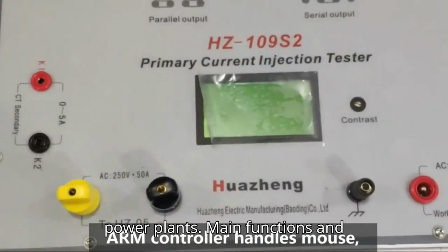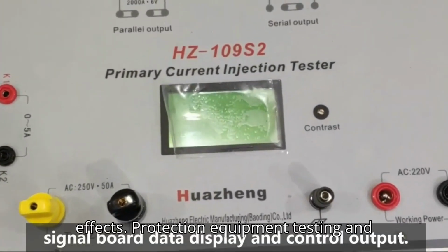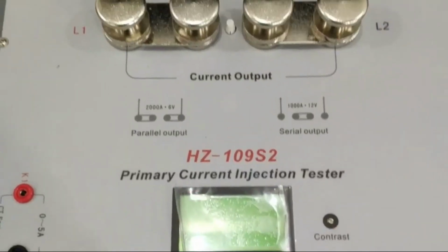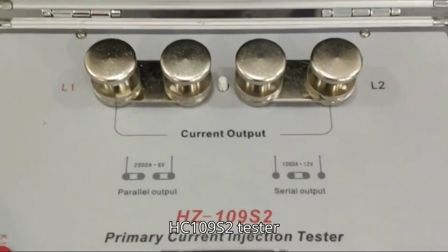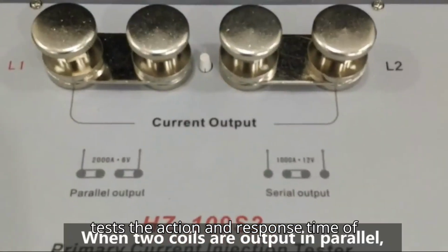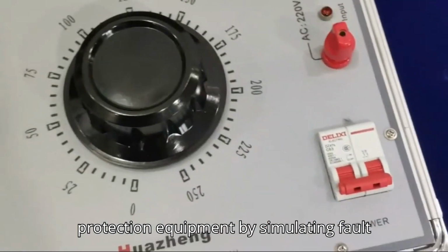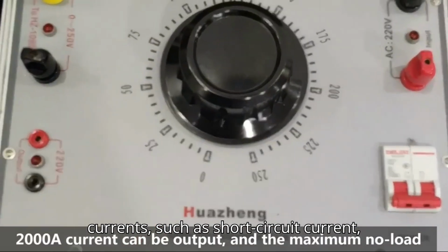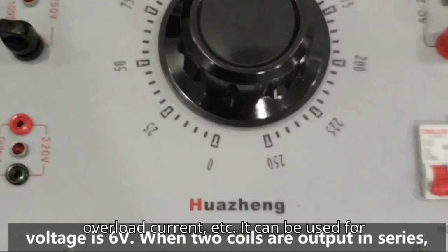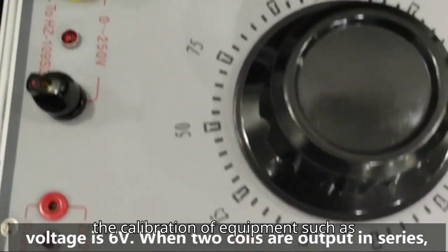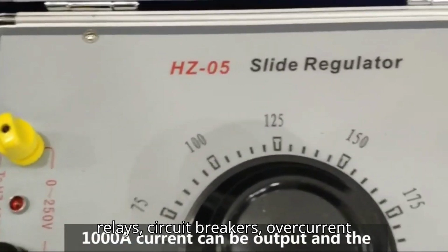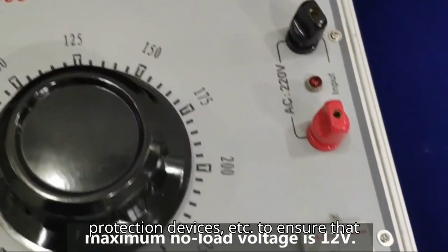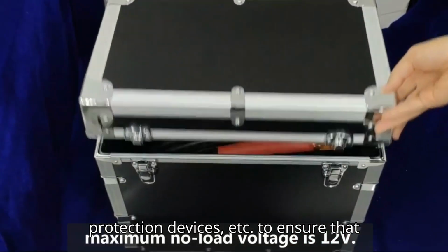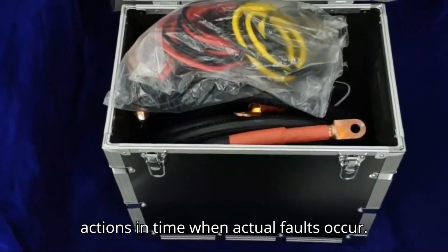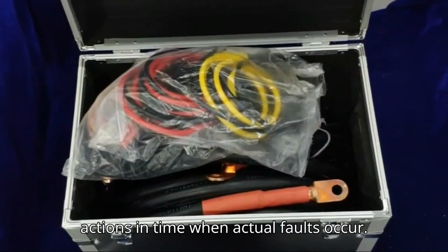Main functions and effects. Protection equipment testing and calibration. The HZ-109S2 tester tests the action and response time of protection equipment by simulating fault currents, such as short circuit current, overload current, etc. It can be used for the calibration of equipment such as relays, circuit breakers, overcurrent protection devices, etc., to ensure that these devices can trigger protection actions in time when actual faults occur.